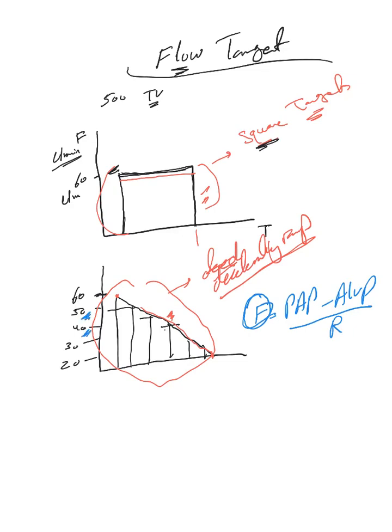It's constant at this point of time. So the only way the ventilator can adapt to this is by going up and down on the proximal airway pressure. So if the patient bites the tube, which means that will increase the resistance, that will decrease the flow, right? But the ventilator is not allowed to do this. It's called to keep the flow the way it is, we told the ventilator to keep it.